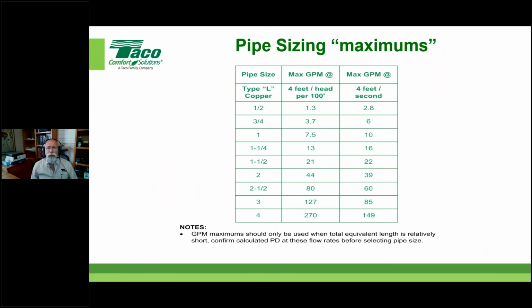So just a little review here on pipe sizing. We're just talking about the maximums that are out there. Whenever you're talking about pipe sizing, you should probably figure out which pipe you're talking about, what type of pipe and what size. In this case, this little chart just references type L copper. But notice there's a couple different columns that say maximum: this one is 4 feet of head per 100 foot of pipe, and this is 4 feet per second. Those are 2 different ways that we look at maximums in our industry.